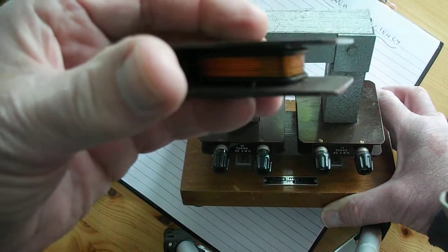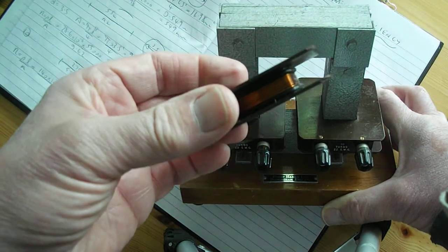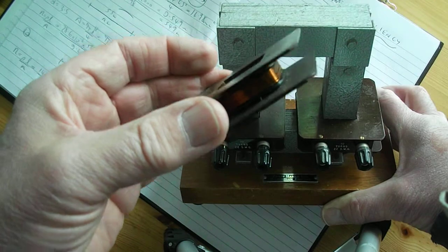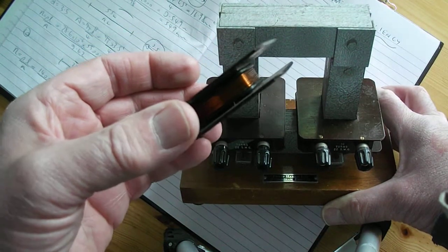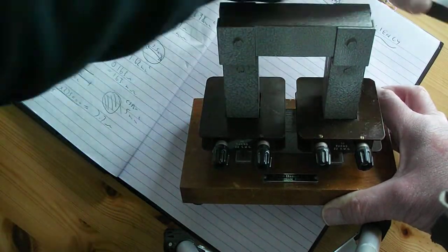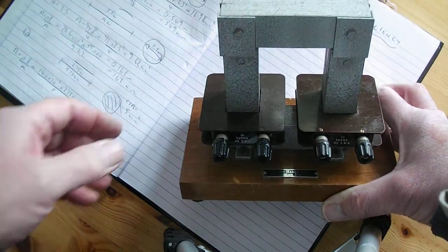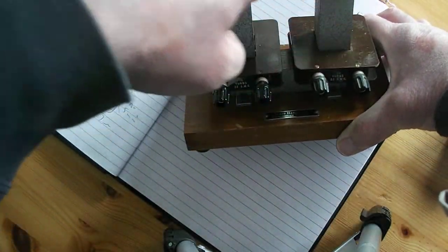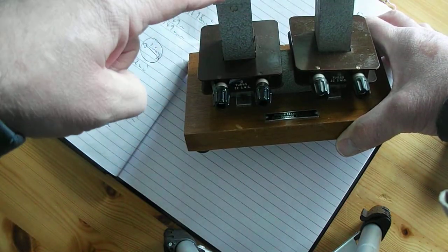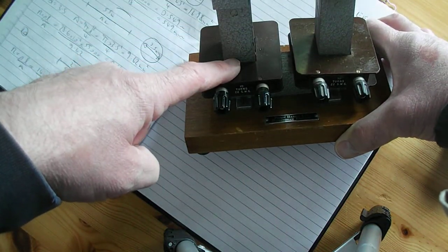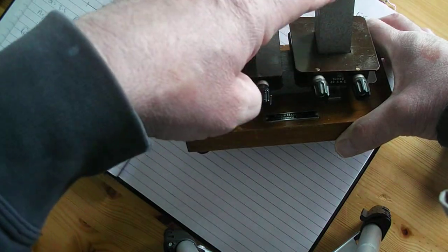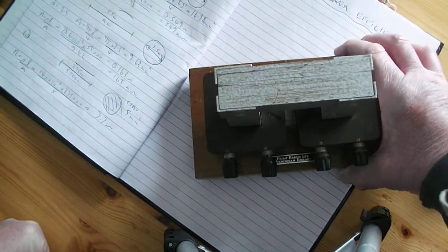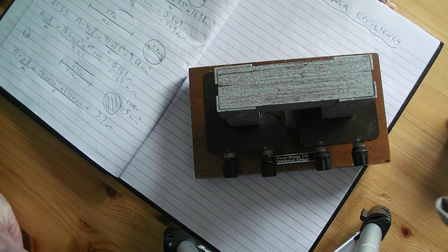And there's another winding here, and this copper winding has resistance, and because it's got resistance, when electricity passes through it, it produces a small amount of heat, and that heat is lost along with the heat that is generated in the core. It's generated through eddy current losses, and it's also lost through hysteresis losses.